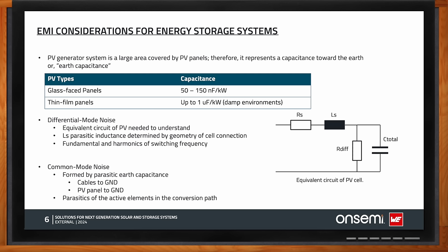Shielding the DC lines can significantly reduce electromagnetic fields, but only if the shield is grounded on both ends with a high-quality connection to earth. Shielded and well-grounded DC lines also offer optimal lightning protection. The length of DC cables affects not only distributed transversal capacitance but also longitudinal inductance, forming a resonant circuit that can cause the PV system to act as an unintended antenna. The impedance of these components varies with cell voltage, solar radiation, temperature, and frequency — making this a complex topic.